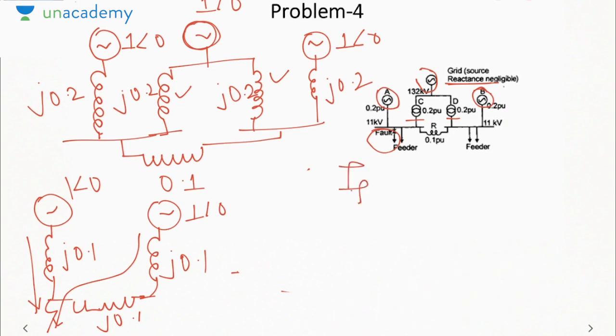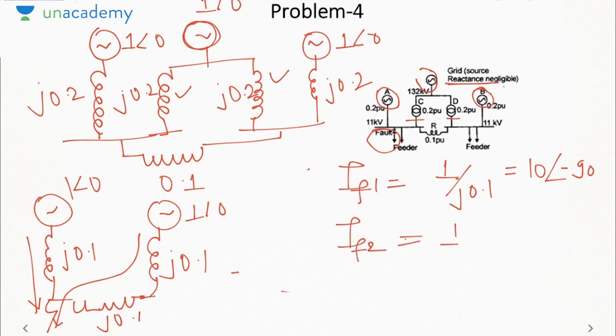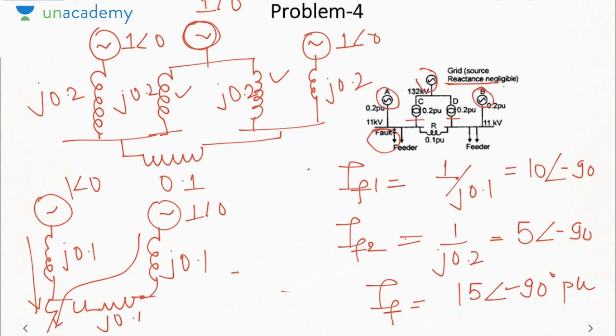The first generator current will be 1 upon J.1, that is 10 angle minus 90. Other will be 1 upon J.2, that is 5 angle minus 90. So total overall fault current will be sum of the two, that is 15 angle minus 90 degree pu. Okay, that will be the fault current in the system.